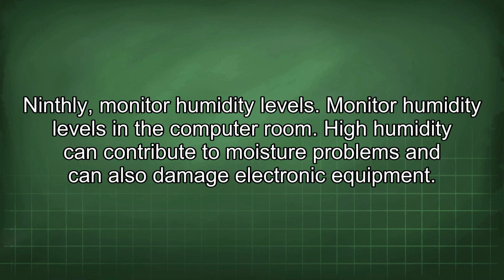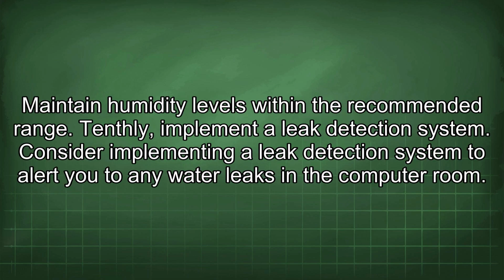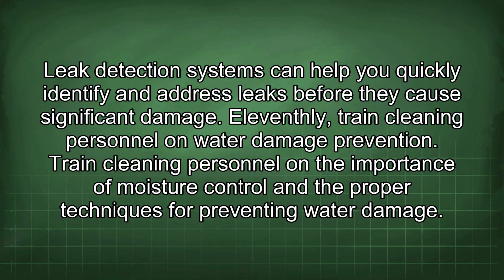Ninthly, monitor humidity levels. Monitor humidity levels in the computer room. High humidity can contribute to moisture problems and can also damage electronic equipment. Maintain humidity levels within the recommended range. Tenthly, implement a leak detection system. Consider implementing a leak detection system to alert you to any water leaks in the computer room. Leak detection systems can help you quickly identify and address leaks before they cause significant damage.